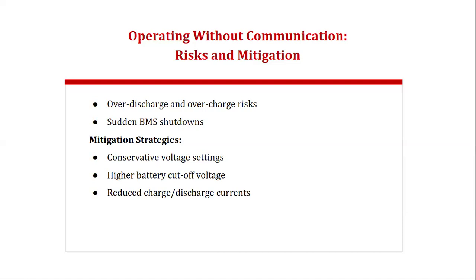You see, to avoid all this wahala, you strategically set the voltage that high, so that when it cuts off at about 48 volts, you still have some energy, you still have a certain voltage level. Then when power comes to continue the operation, the battery is still live, so it will be able to connect and start to charge. Then higher battery cutoff voltage, so you have to set, which is what we just mentioned. That's the higher battery cutoff voltage.